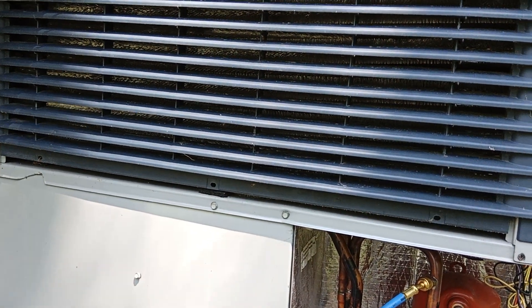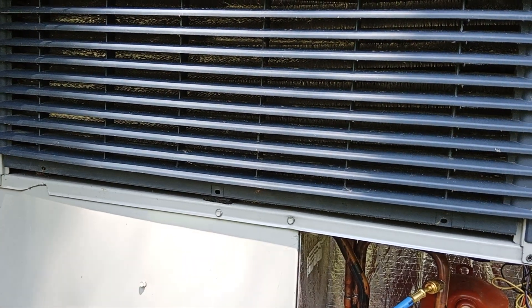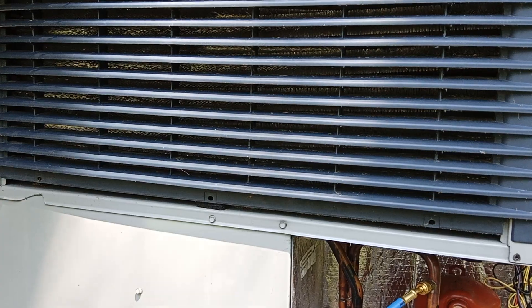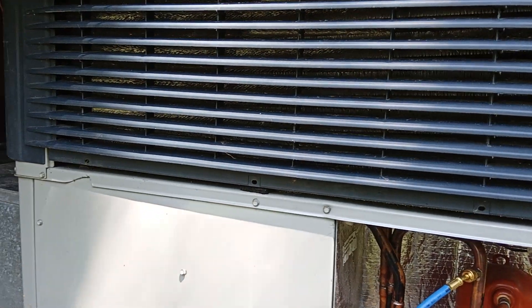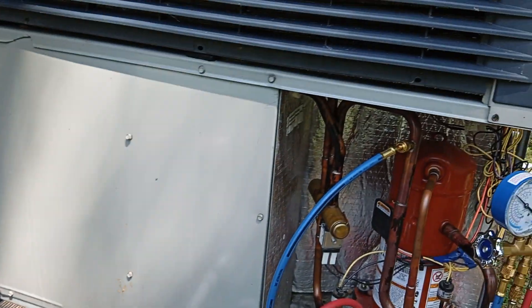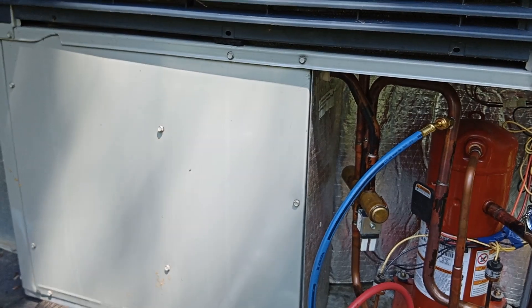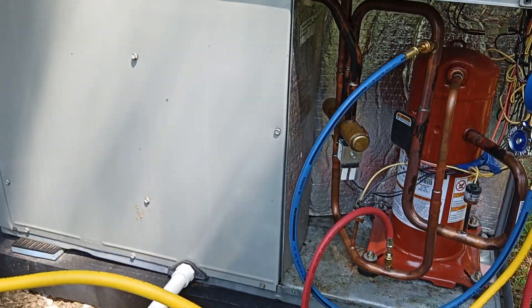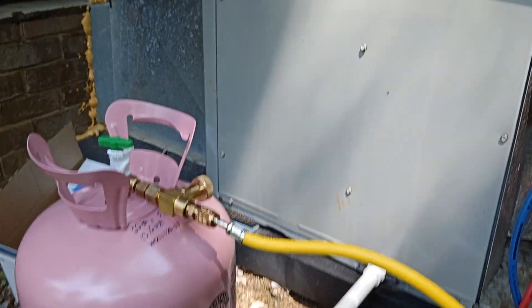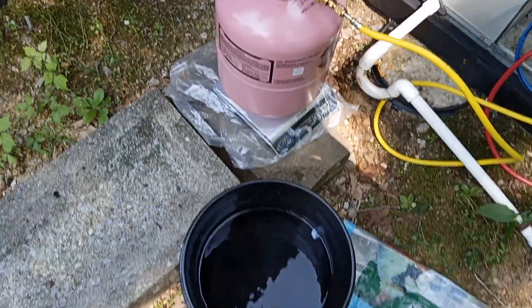That goes to show the surface area of that huge coil — it's probably five or ten times the surface area of that can, so very sensitive to delta T. When the charging rate's low but it's working on 75 toward 80 degrees, this is going way too slow on the heating pad, so we're going to use a little magic trick called hot water.